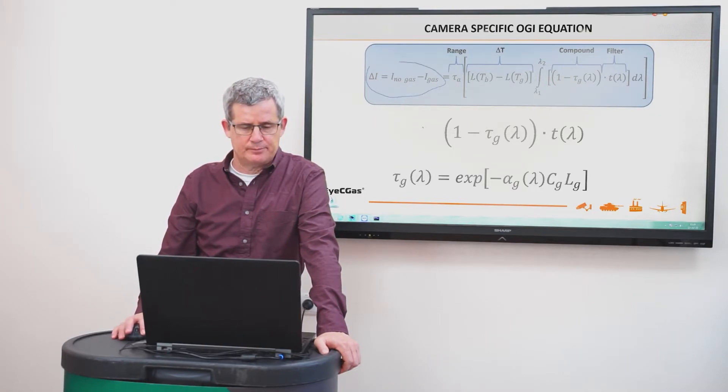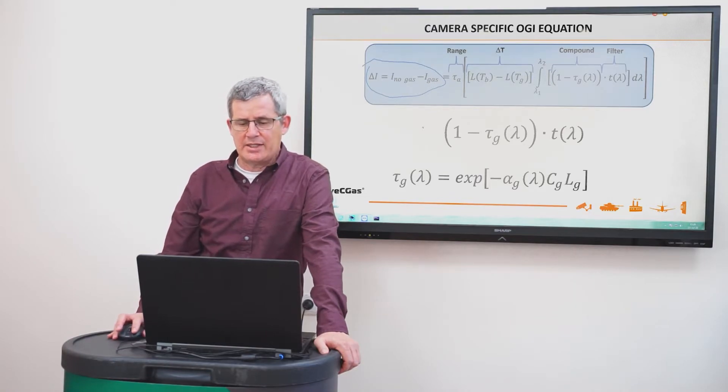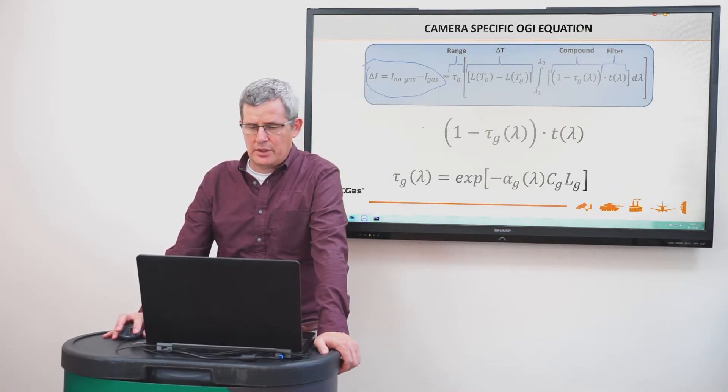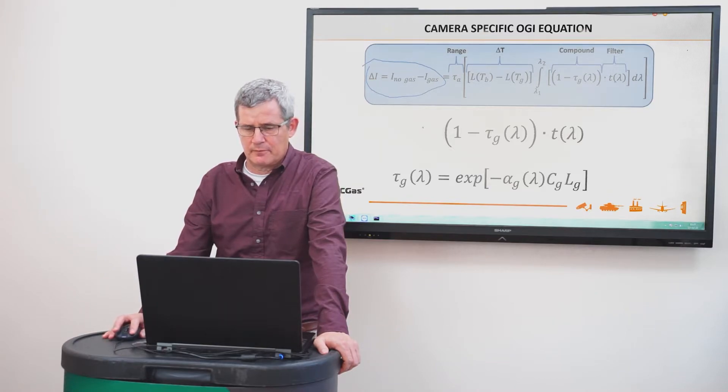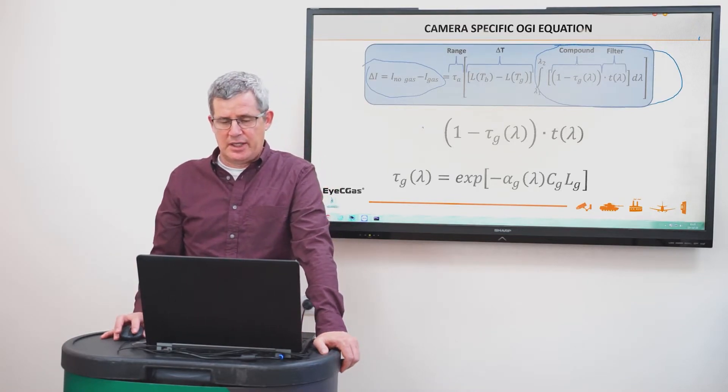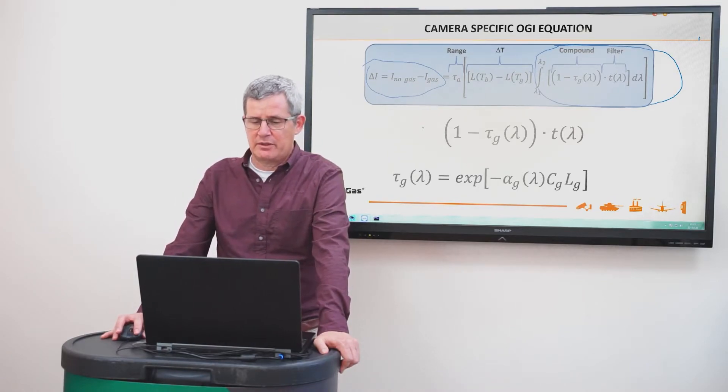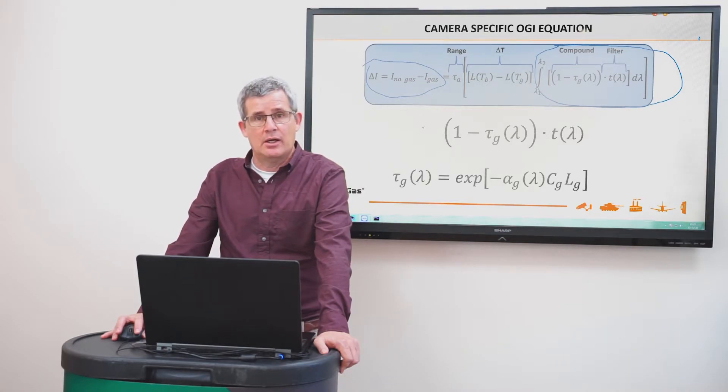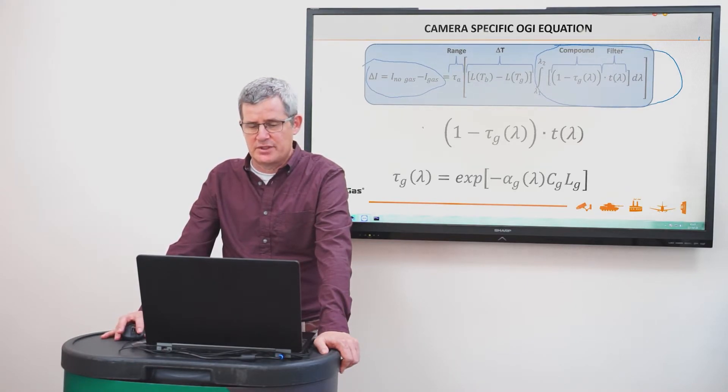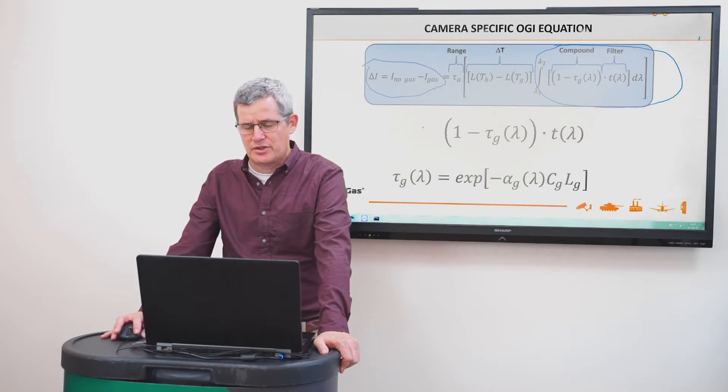We have the contrast here. On the right side, we have the compound specific response that is a function of the camera's filter and the absorption coefficients and the concentration of the gas. It's very important to understand that this is the underlying physics. It's not dependent on the scene temperature differences, it's independent of the temperature, only on the absorption coefficient and the concentration.